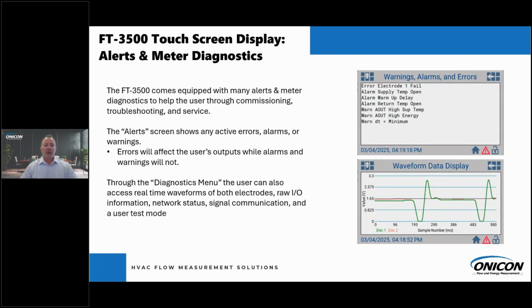As well as alerts, so for any type of error alarm, or if you really don't know what's going on with the meter, you can quickly go into one of the screens and see those failure modes. As well, when you contact the tech support team, this is great information for us to be able to troubleshoot over the phone. And in the bottom right-hand of your screen there, you're able to provide a waveform. If you notice, the green waveform on electrode 1 is communicating correctly, and then you see electrode 2 does not provide any data. So it's a great diagnostic menu to dive into what is actually happening over the lifetime of your meter in the field.